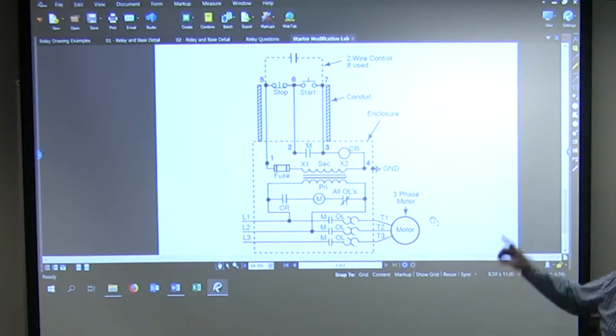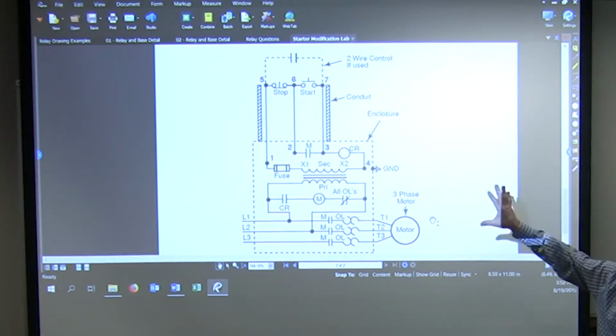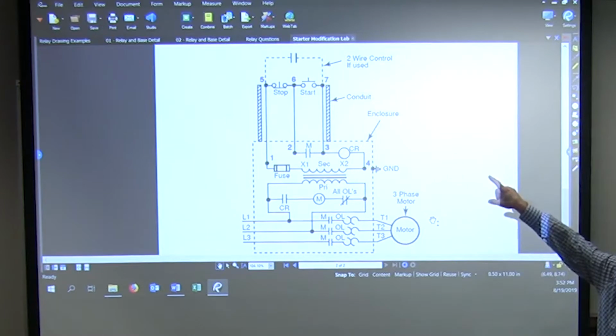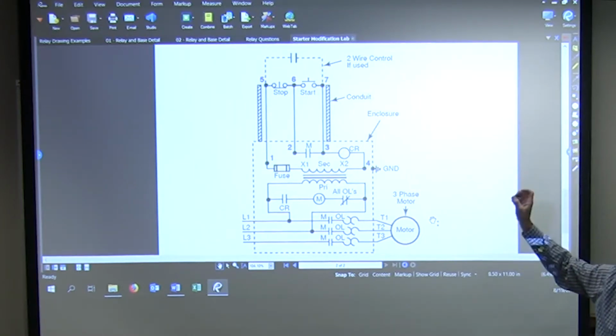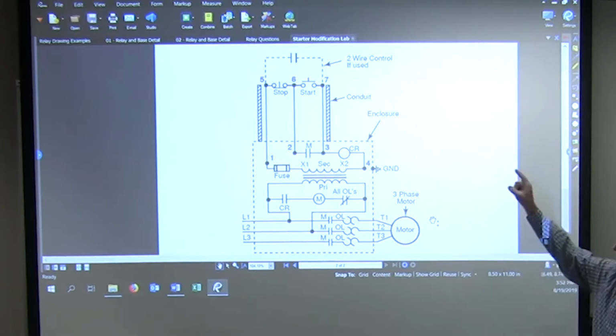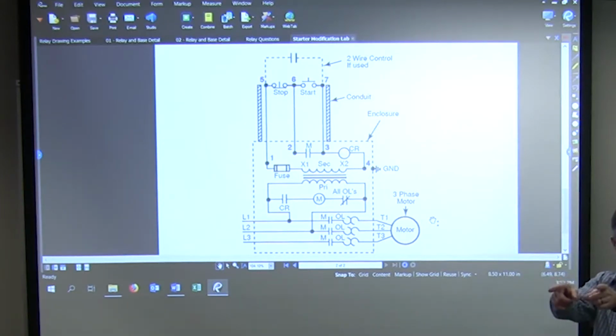Now, if I wire this and leave everything just as it is and add the dotted, normally open contact at the top, what will this do if that is my building automation control signal? It'll never stop. Start up and don't stop. Okay, so from both of you, it'll start and not stop unless it's told to stop. Unless there's a power outage. There's got to be something to push that stop. Okay, so let's talk about it.